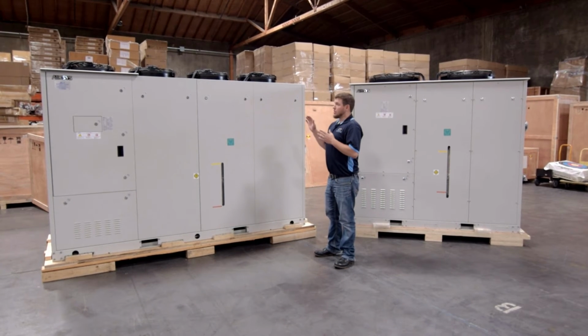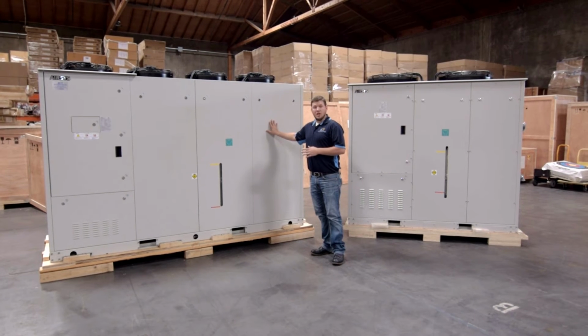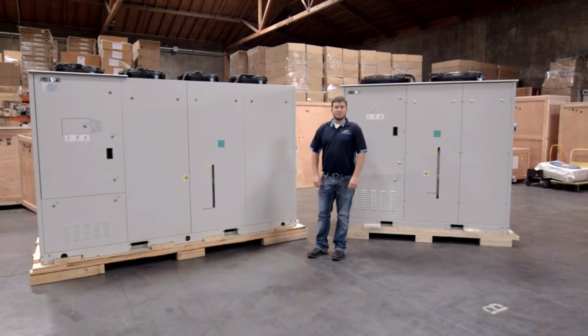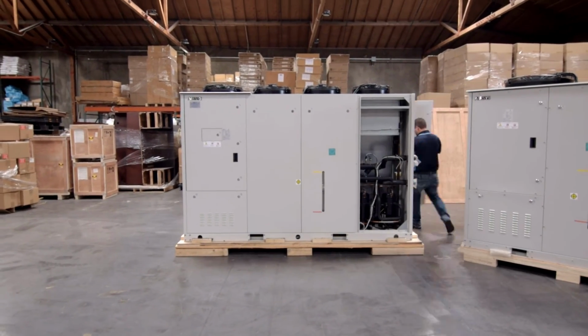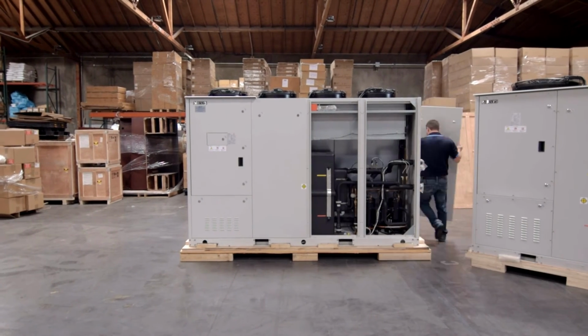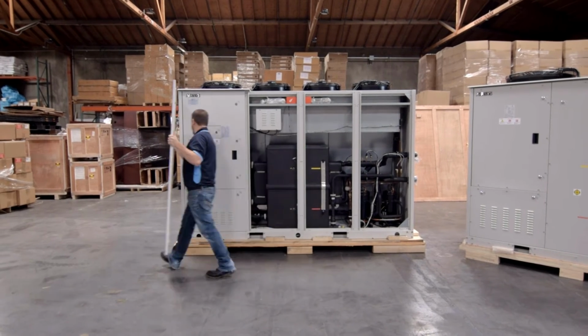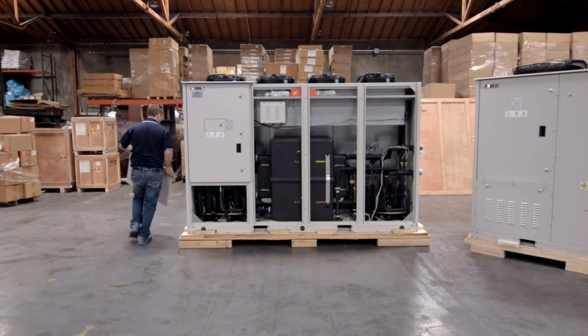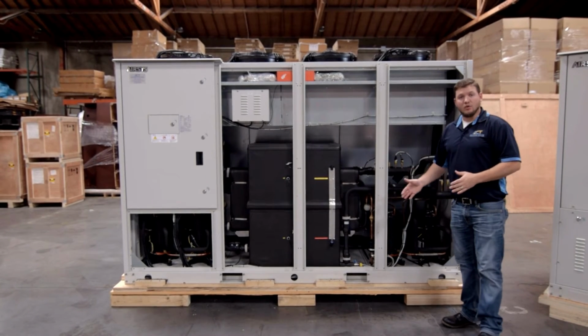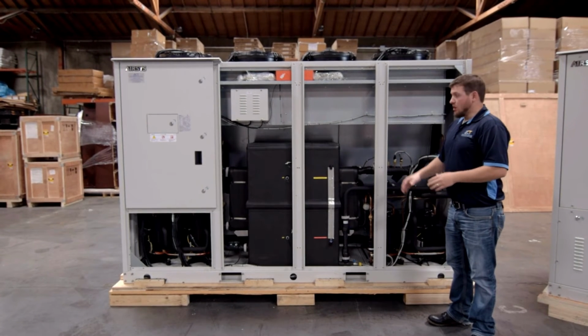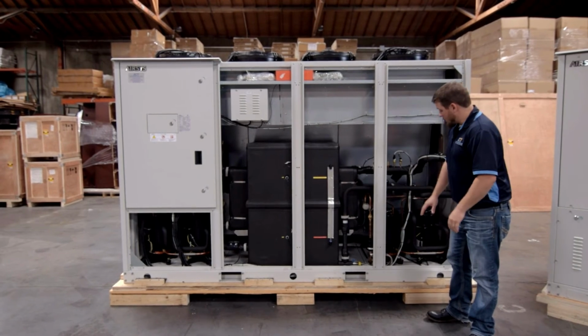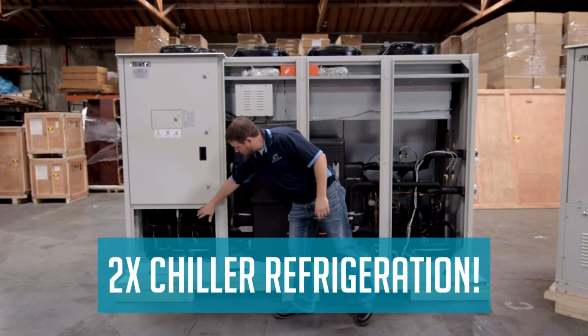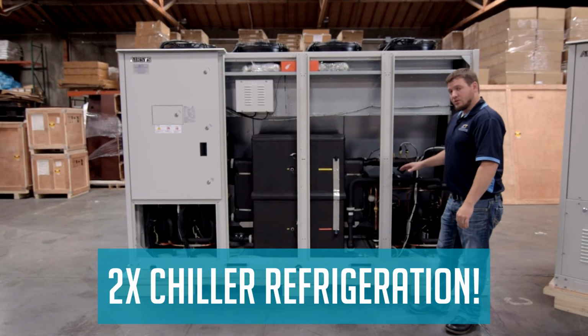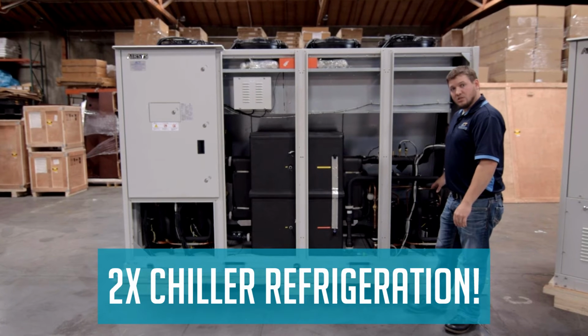What I'm going to do now is go ahead and remove these front panels, and we're going to go into more detail about a fully redundant chiller. Now with the panels removed, let's talk about the value of a true, fully redundant chiller. Let's begin with the refrigeration systems. As you can see, there are two chiller refrigeration systems. Each one of these systems is completely separate from each other. This allows us, if there is a failure of a component in one of the systems, it does not shut down the chiller, as the other system is able to operate the load.